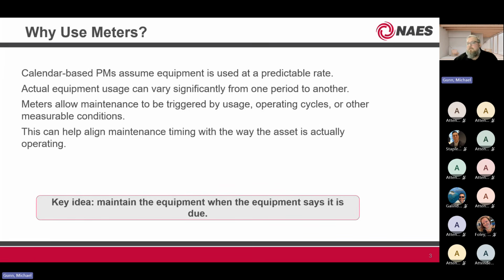So why do we use meters? I can't tell you how many times I've done an assessment and every single PM is calendar based. It's kind of like your car: if you do your oil change every 3, 4, 5 months instead of based on how many miles you've driven, you're probably over-maintaining your car, or potentially under-maintaining it depending on how much you drive. A lot of maintenance is dependent on run hours and actual system conditions, so using a meter allows maintenance to be triggered by that meter and actual plant conditions.